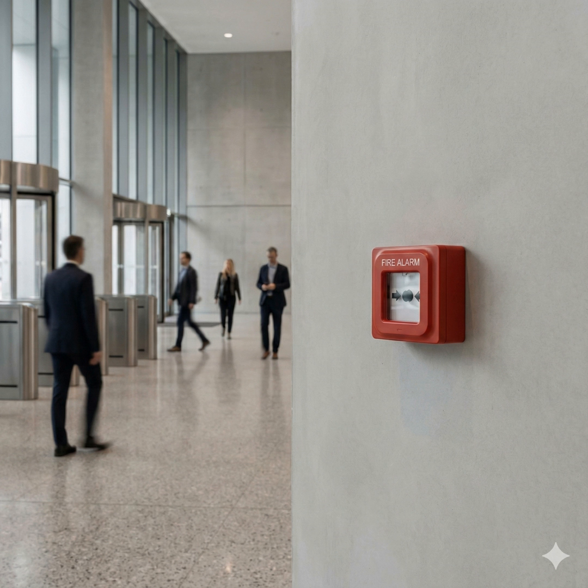It is. It's a high reliability requirement, and it's designed to prevent unnecessary shutdowns or evacuations in mission-critical places. Think data centers, hospitals, specialized manufacturing plants. The system logic actually mandates confirmation from multiple input devices, often sensors in physically separate zones, or even requiring signals from sensors using different technologies like smoke and heat before it escalates to a full alarm. Which just gives you much higher confidence in the activation. Absolutely. It prevents a single false trigger from steam or dust from shutting down an essential operation for no reason.